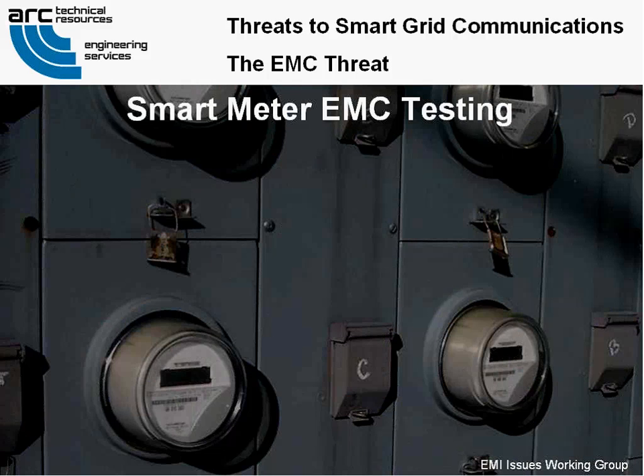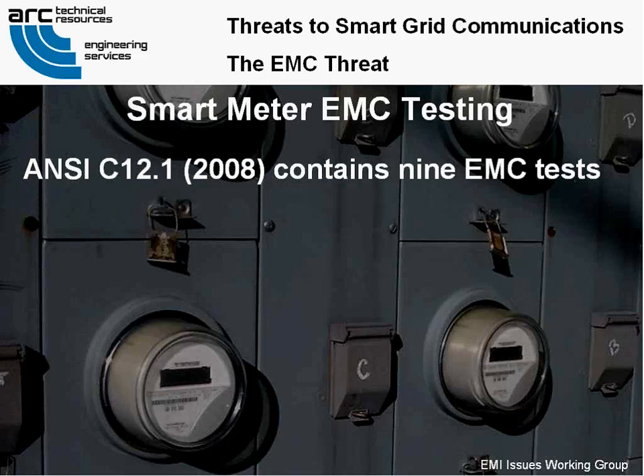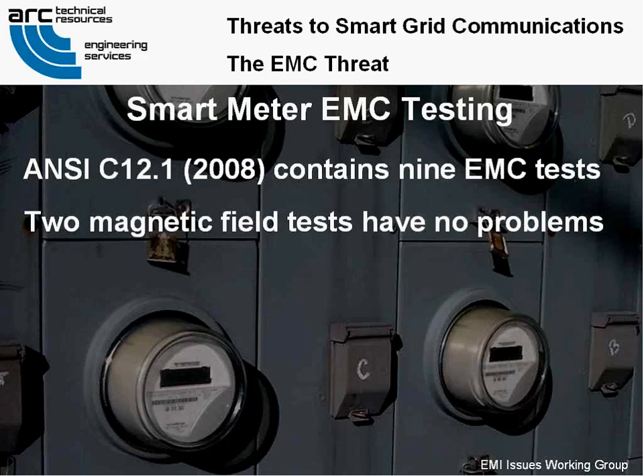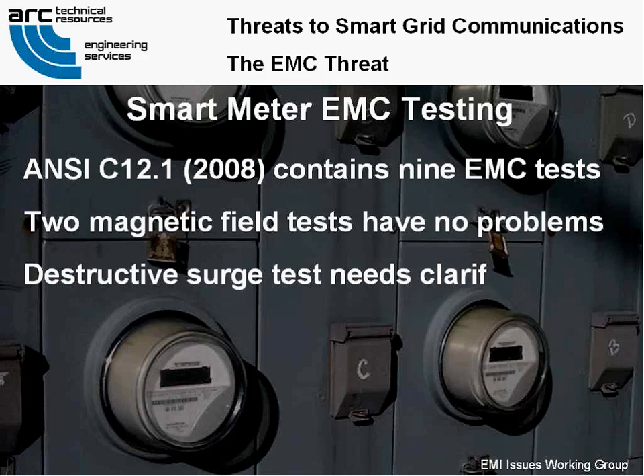Smart meter EMC testing. Outside the substation fence and distribution, or Zone B, smart meter EMC testing has been found to be inadequate. ANSI C12.1 contains 9 EMC tests. Only the 2 magnetic field tests are free of problems. They each have established test levels and methods, a clear acceptance criteria to be assessed during the test, and require that the meter be operating normally during the test. The destructive surge test needs more clarification about the number of strikes, their polarity, and some missing phase angles. The other 5 have serious issues.